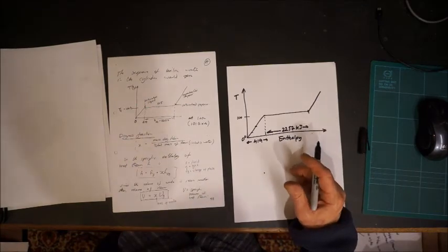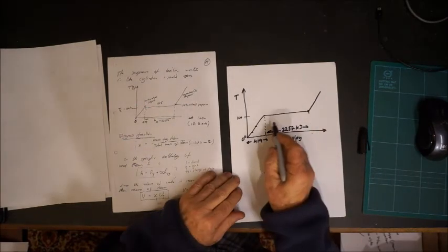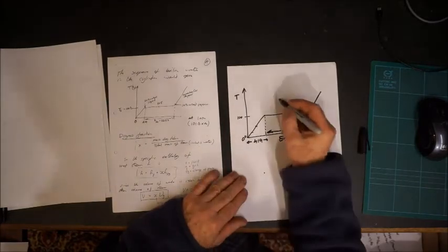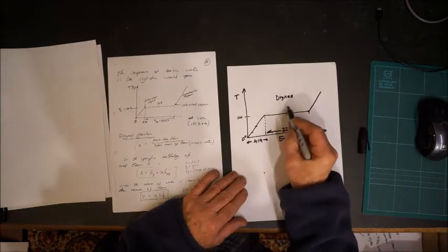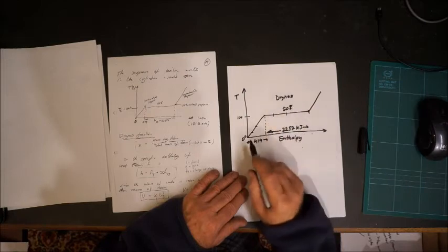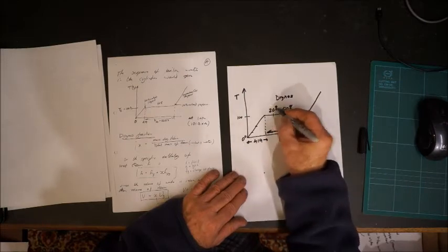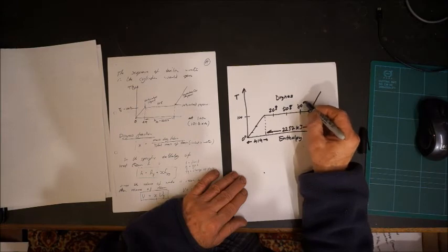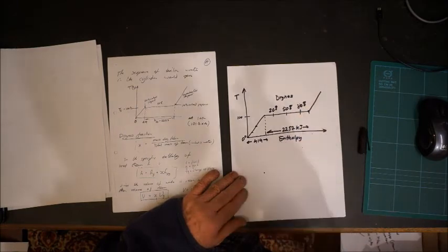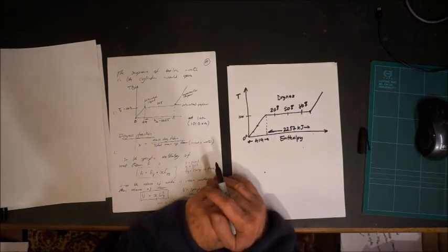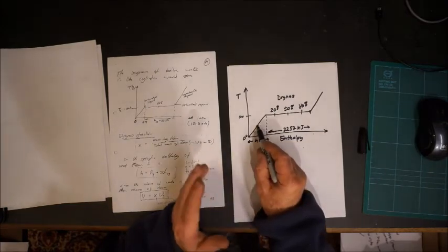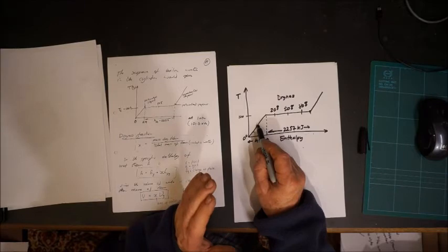Now it's a thing called the dryness factor. And the dryness factor is just simply how far you are along this line. So if I'm talking about dryness, if I'm, say, there, it's 50%. If I'm there, I'll say 20%, 80%. And the amount of energy to make the steam, and this is probably the most important thing, just depends on how far you are along here.